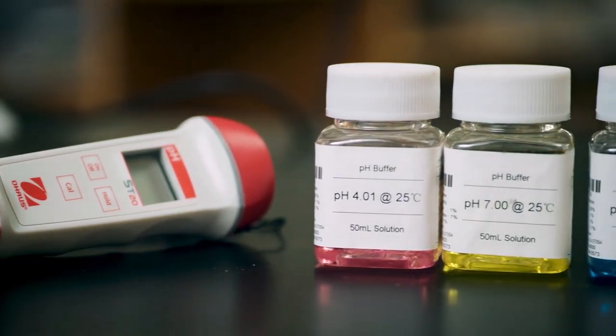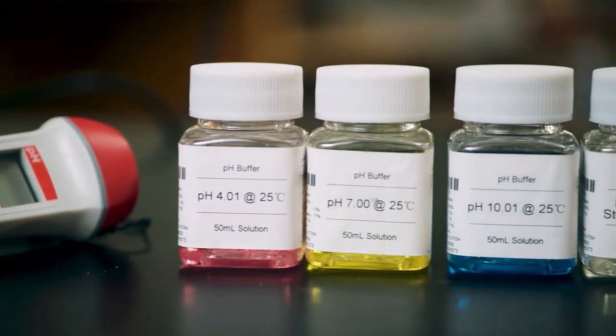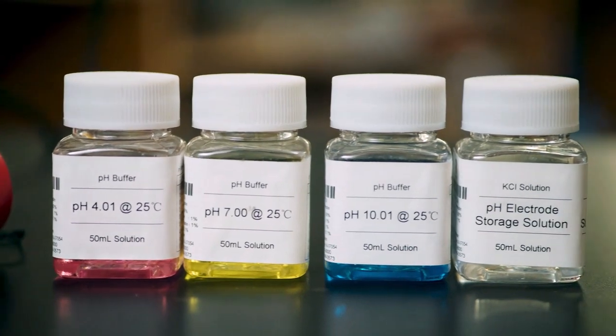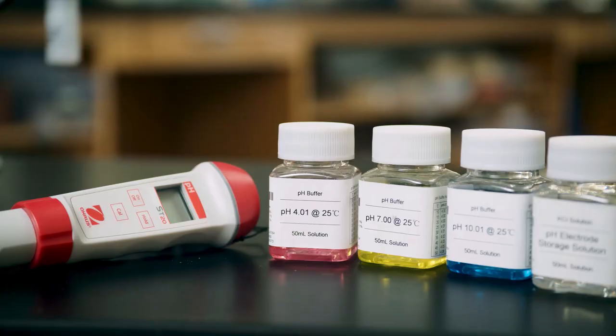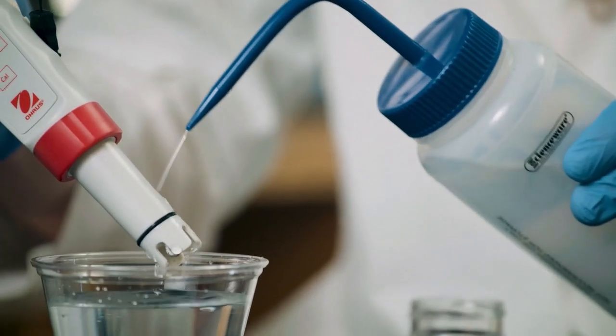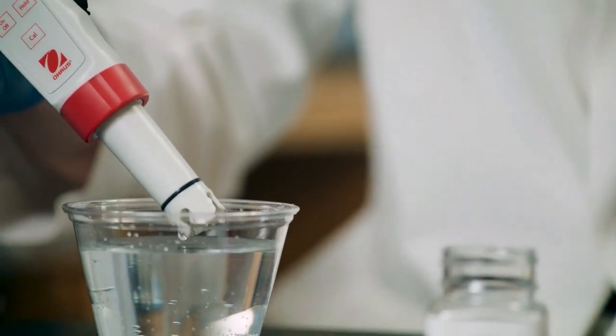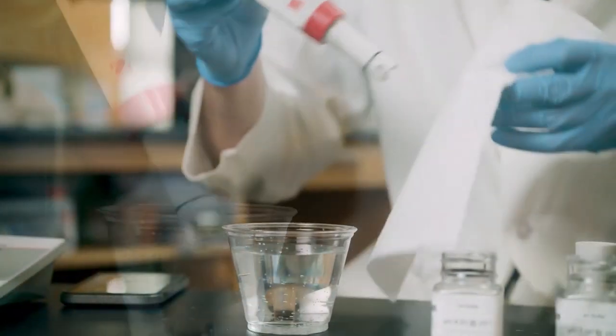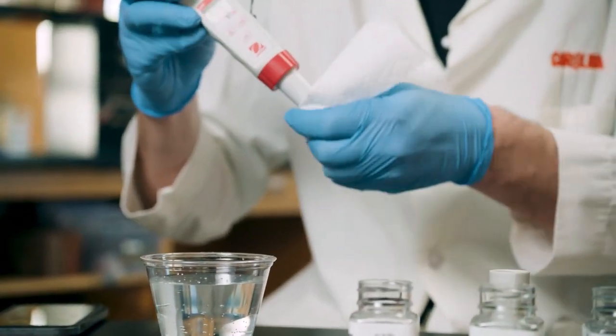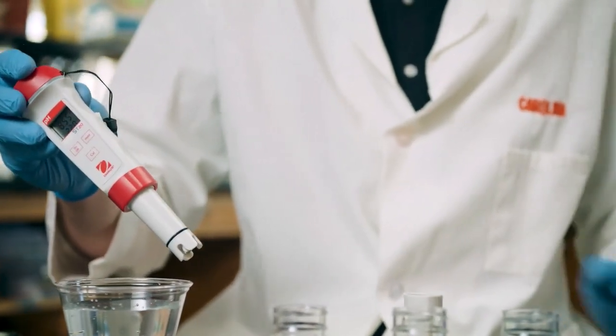This video demonstrates the 3-point calibration of the Ohaus ST20 pen meter. To calibrate, you will need the pen meter, distilled water, a soft clean cloth, a pH 4.01 buffer solution, a pH 7.0 buffer solution, and a pH 10.01 buffer solution. Before use, remove the protective cap. Rinse the pH electrode with pure distilled water and wipe clean. Be careful not to scratch the bulb of the pH electrode.